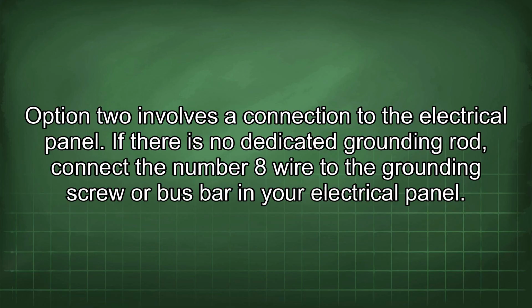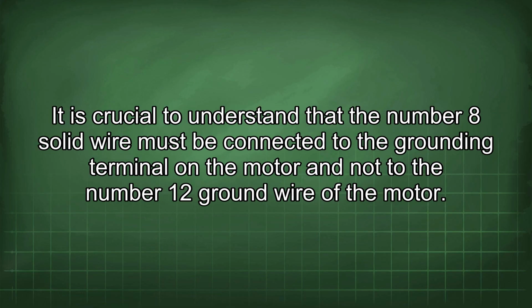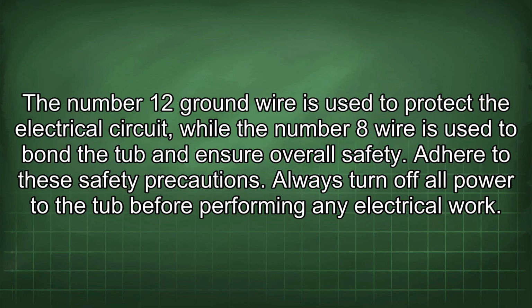It is crucial to understand that the number 8 solid wire must be connected to the grounding terminal on the motor and not to the number 12 ground wire of the motor. The number 12 ground wire is used to protect the electrical circuit, while the number 8 wire is used to bond the tub and ensure overall safety.